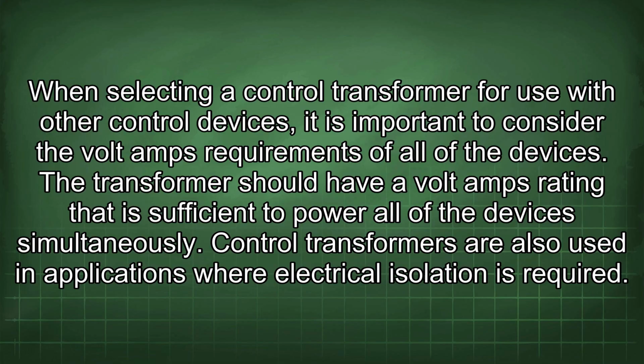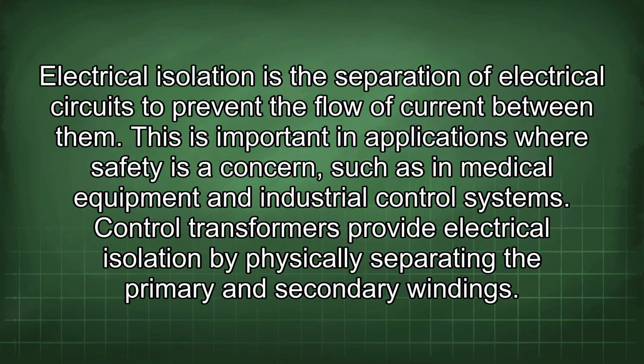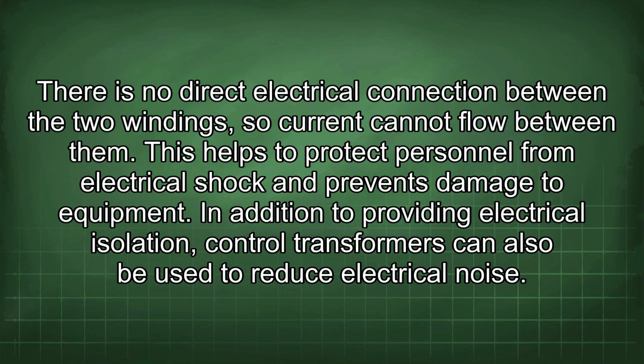simultaneously. Control transformers are also used in applications where electrical isolation is required. Electrical isolation is the separation of electrical circuits to prevent the flow of current between them. This is important in applications where safety is a concern, such as in medical equipment and industrial control systems. Control transformers provide electrical isolation by physically separating the primary and secondary windings. There is no direct electrical connection between the two windings, so current cannot flow between them. This helps to protect personnel from electrical shock and prevents damage to equipment.